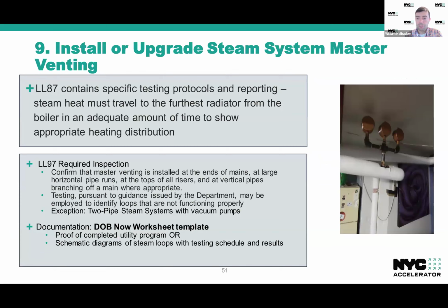So Local Law 87 does have a parallel here. It does have some testing requirements to see if your building needs to install master venting. So you can basically set up some sensors to monitor temperature between the boilers and the ends of the steam mains to see how quickly steam travels from the boiler to the ends of the distribution. If your steam takes too long to reach the ends of mains, then you need to install master venting. So just see that you've done this work already under Local Law 87. You might have already done it.